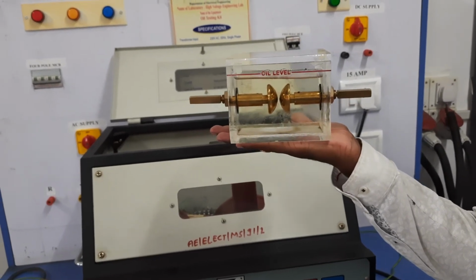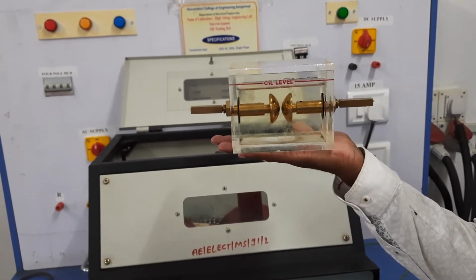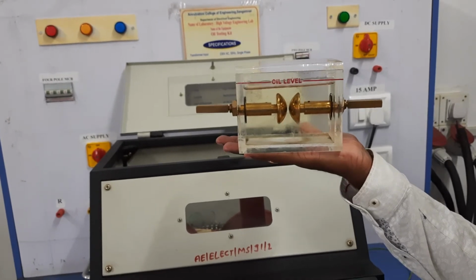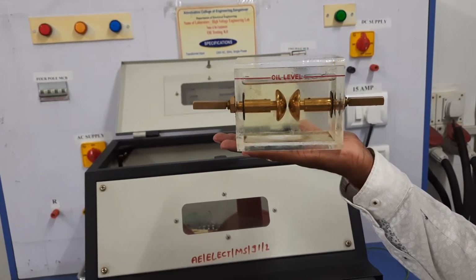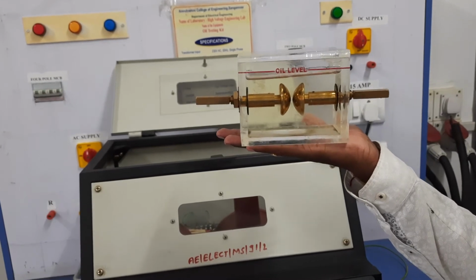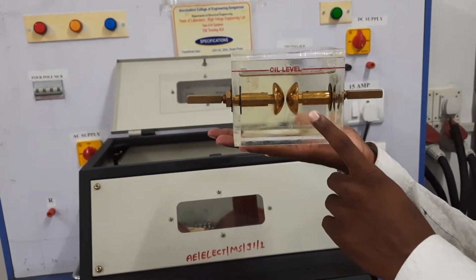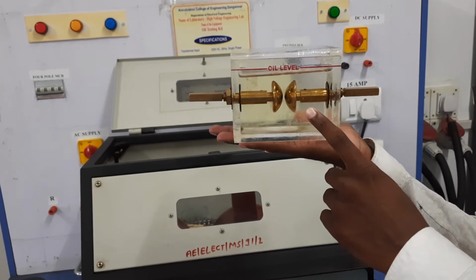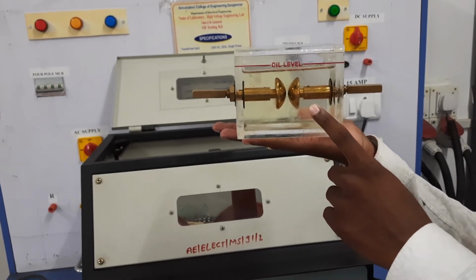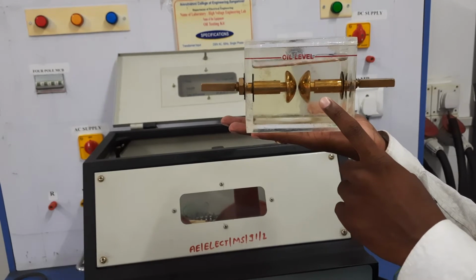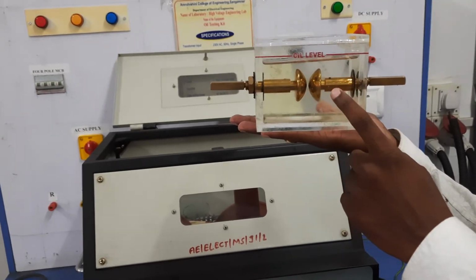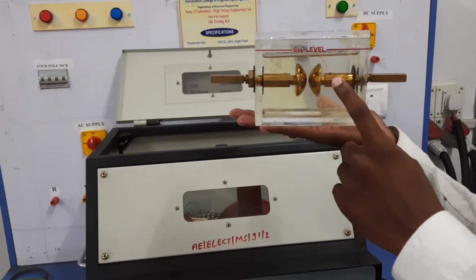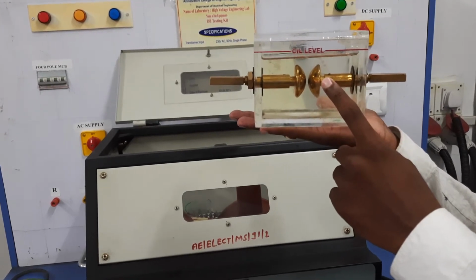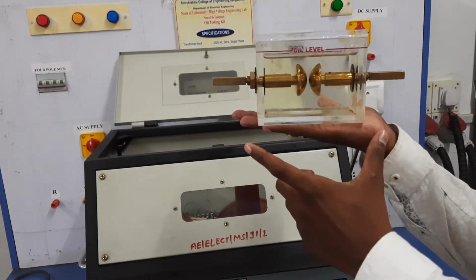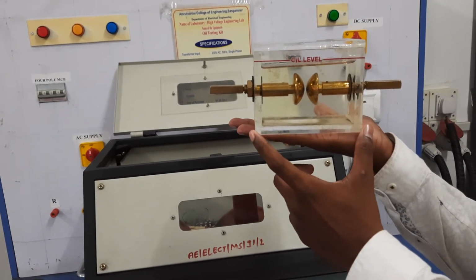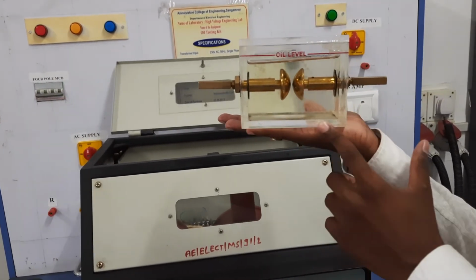The basic specification of this test cell is, as per IS 6798: the electrode used in this liquid is copper. The shape of the electrode is semi-hemisphere. The distance between the two electrodes is 2.5 mm.